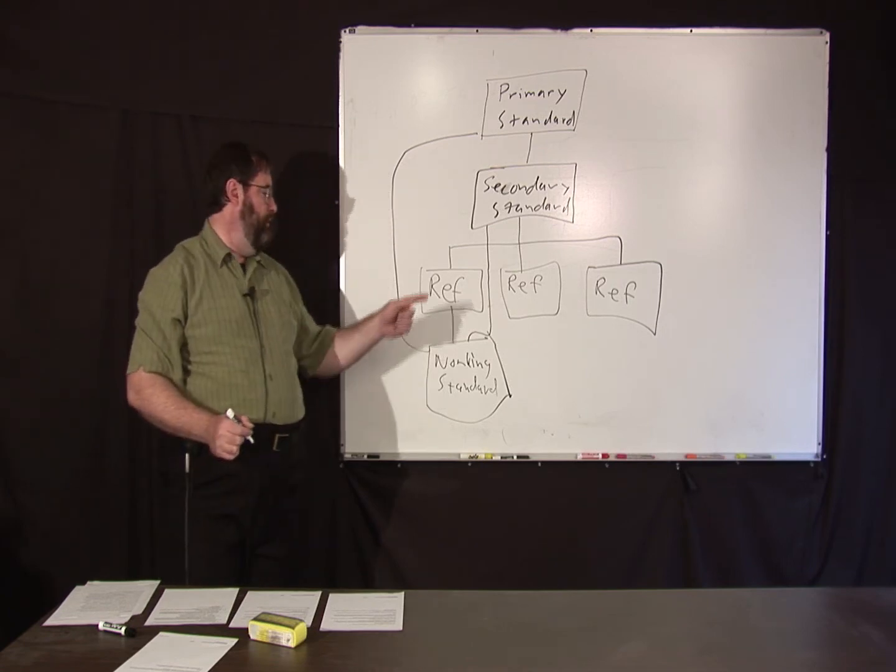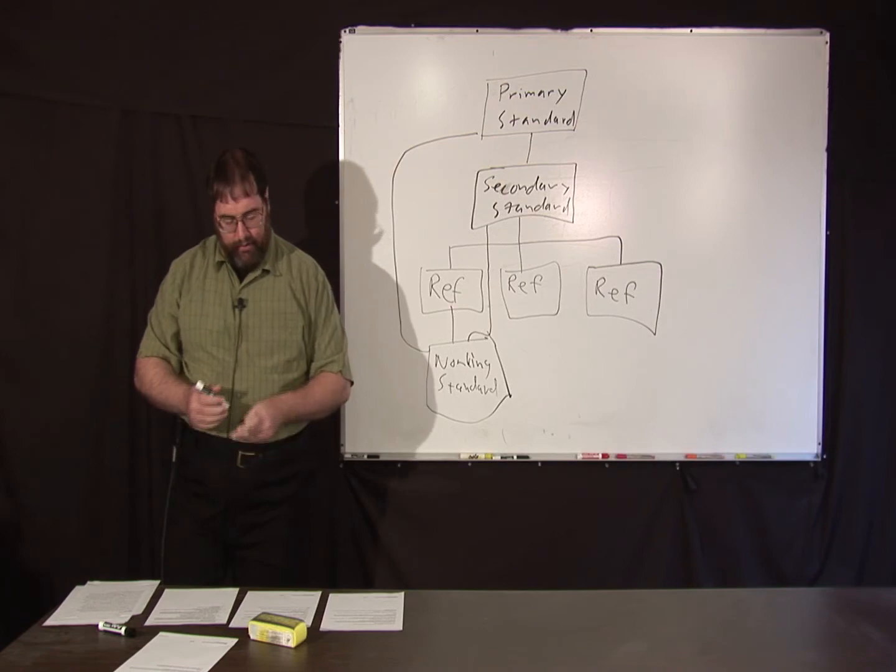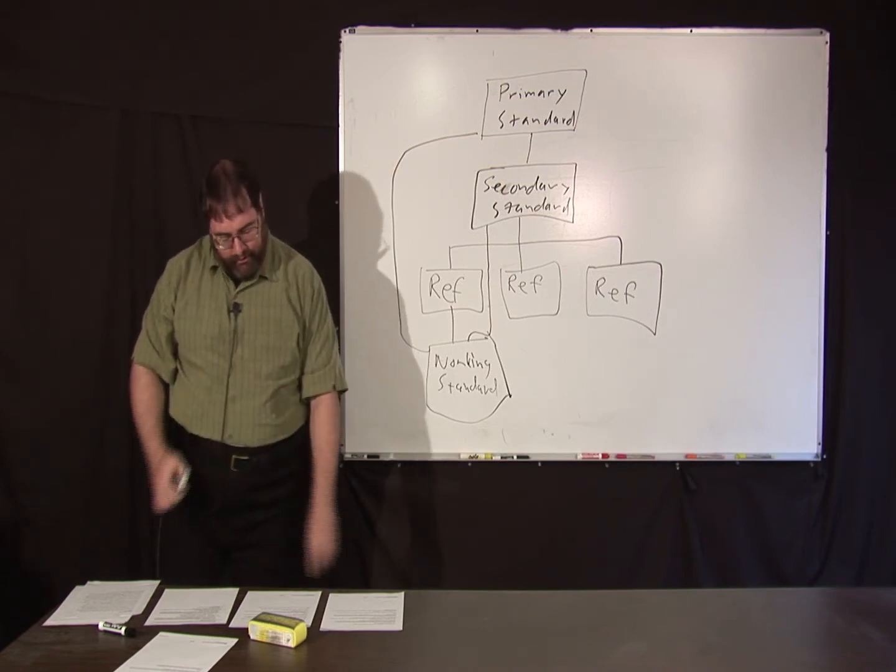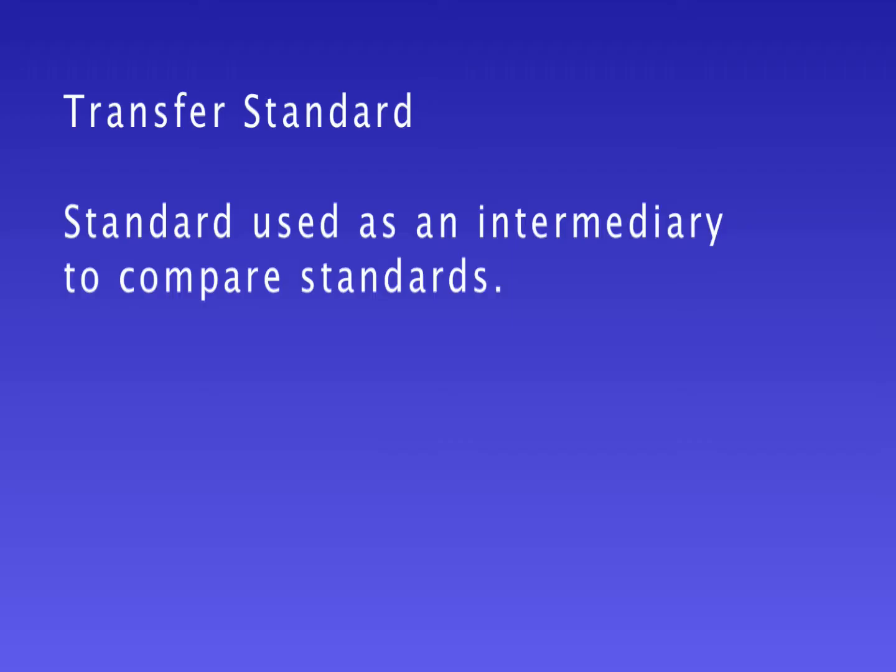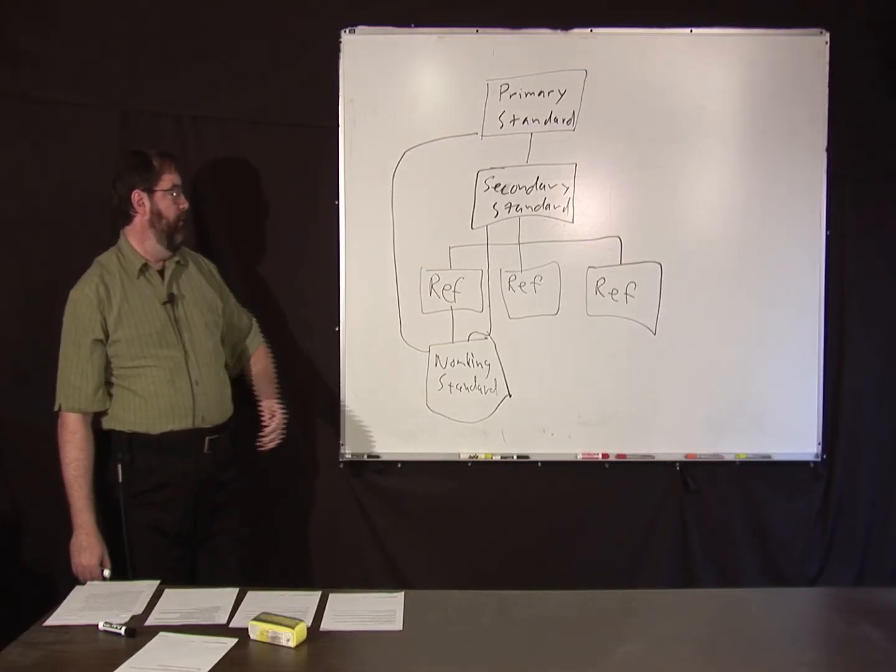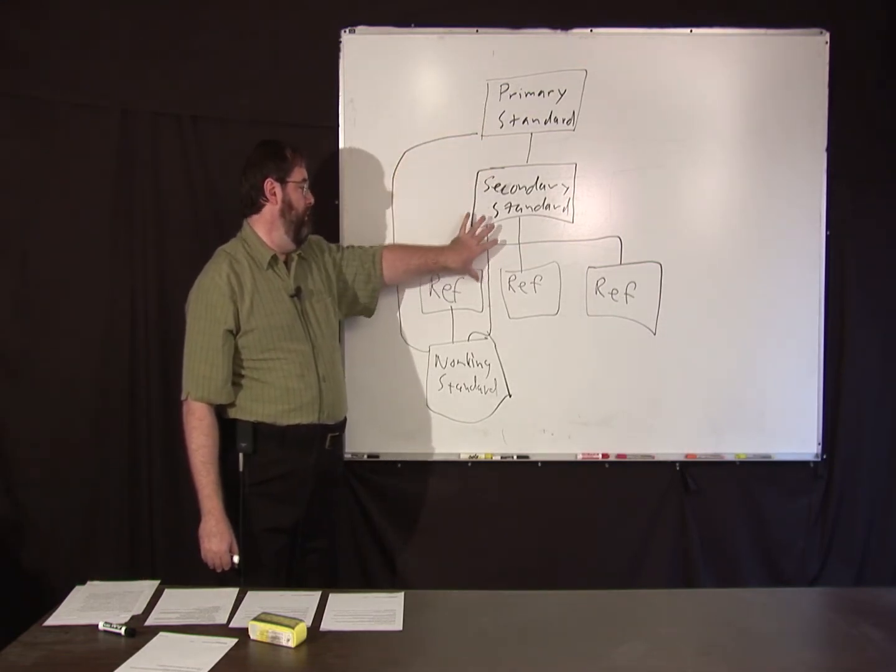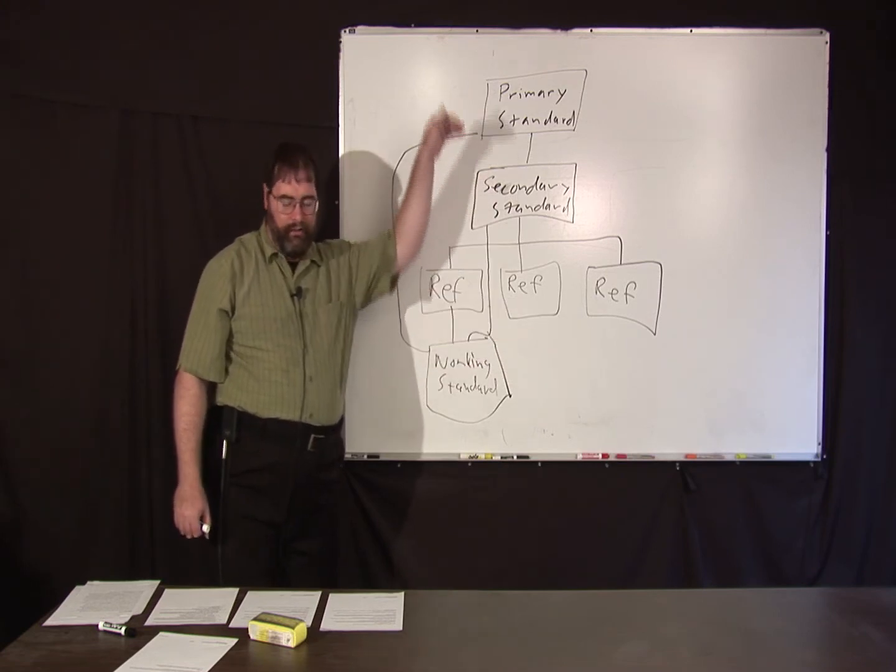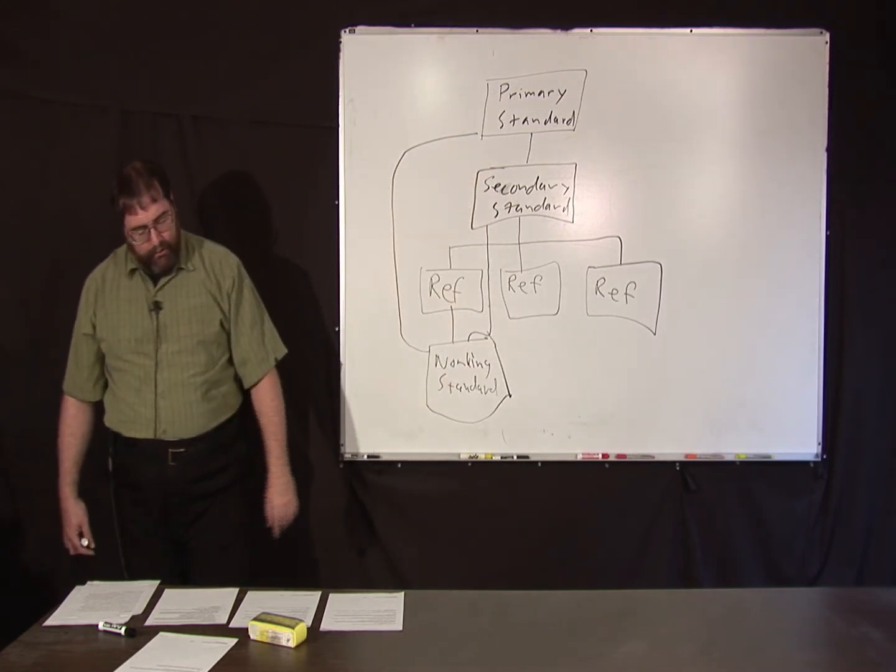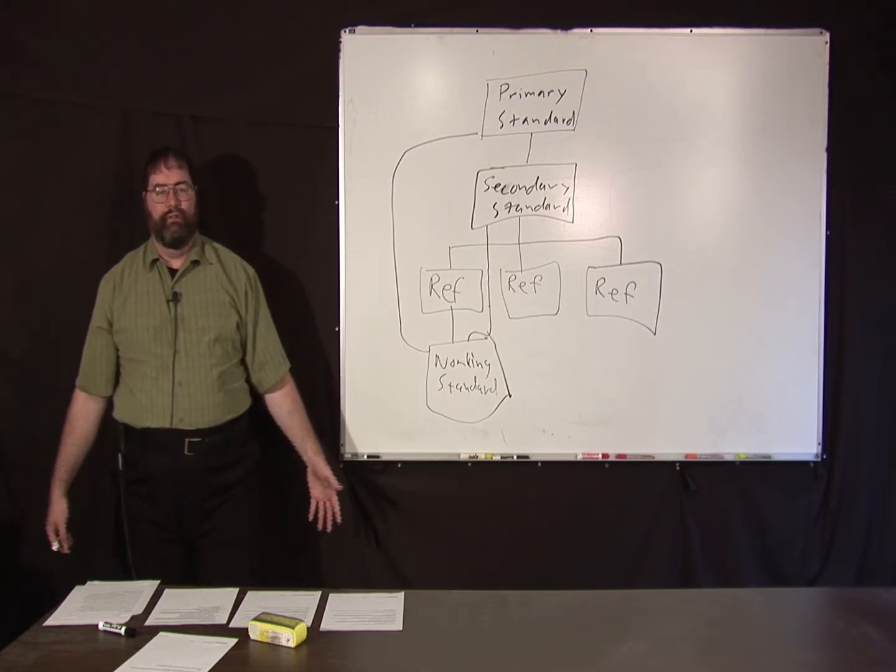And then there's standards that are used to implement the intercomparisons. And those are defined as transfer standards, a standard used as an intermediary to compare standards. There might be something used, the instrumentation used to compare the different levels of this hierarchy of calibration. And this goes right down to the measurement of whatever it is you're trying to measure.